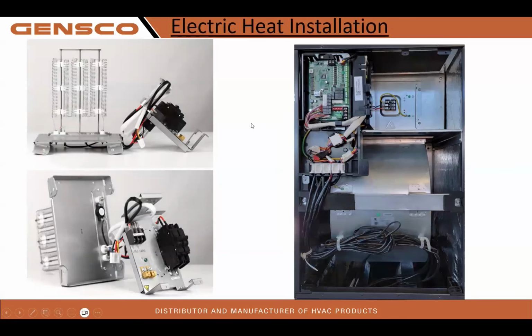Here's a look at our electric heat installation. Here we've got what appears to be a 5 or a 10 kW heat kit. Very simple to install. It's actually just going to remove 4 screws right here. First, you're going to have to remove this control board. It is 3 screws, 1 right there and 2 up at the top, and this control board just merely hangs right out of the way. Then we will go ahead and remove 4 screws from the backer plate and install our heat kit.